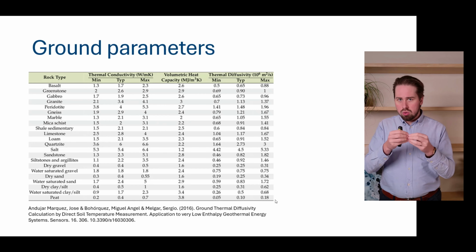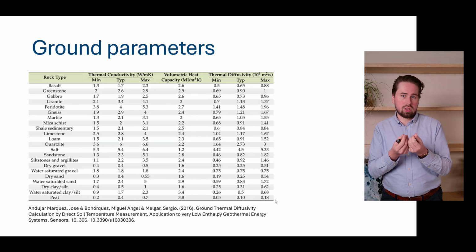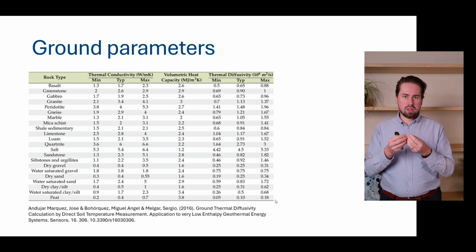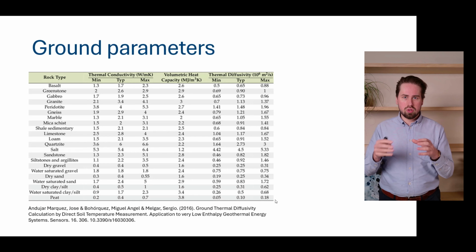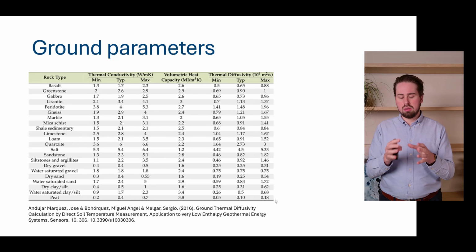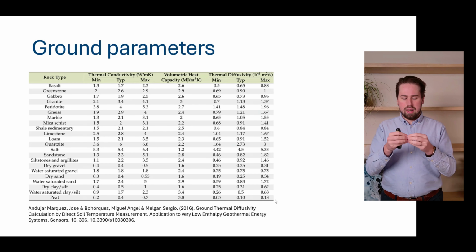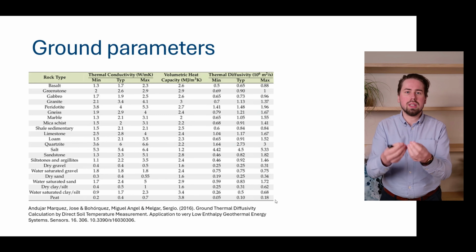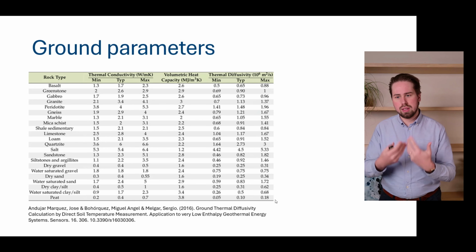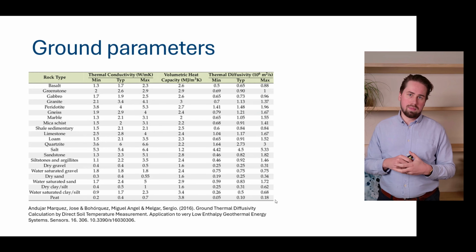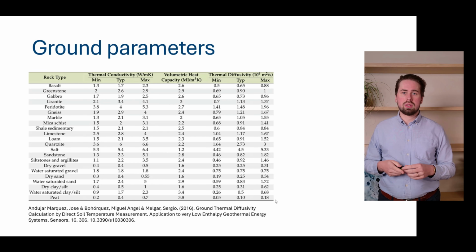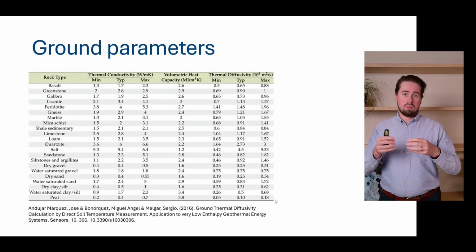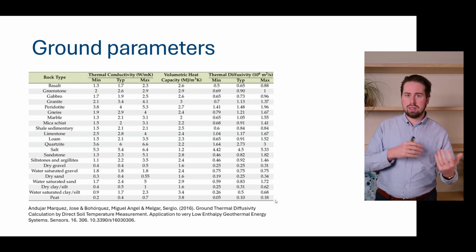But when there is no groundwater and it's unsaturated soil, there are voids. And as you perhaps know, a void is an insulator that can pass no heat through a vacuum. So when there is air trapped, there is no heat transfer possible, so the conductivity is also worsened. So that's also important when you're using these ground parameters for your project, that you know: is my ground saturated or not?